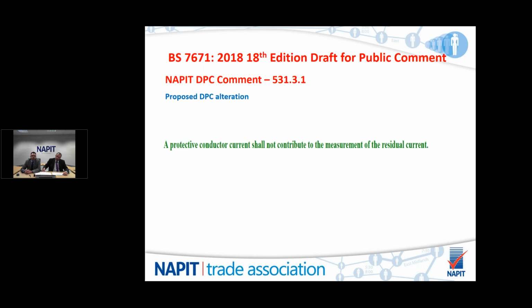And the next one is, we have another comment on Regulation 531.3.1. And the proposed DPC alteration states a protective conductor current shall not contribute to the measurement of residual current.